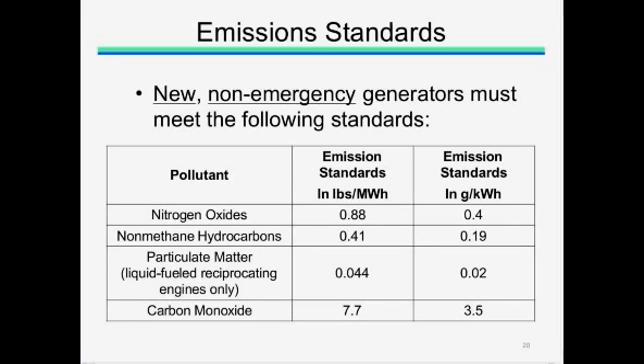The current slide shows the emission standards which would apply to new non-emergency generators under the model rule. And again, these standards are represented as pounds per megawatt hour and gram per kilowatt hours for comparison purposes. The standards equate to the most stringent Tier 4 standards of the non-road rules. Although the Tier 4 standards do not take effect until 2014, which is a full 3 years away, the standards are included in the model rule to allow a 3-year time frame for the state to consider adopting the model rule, go through a regulatory development process, and allow adequate time for implementation.